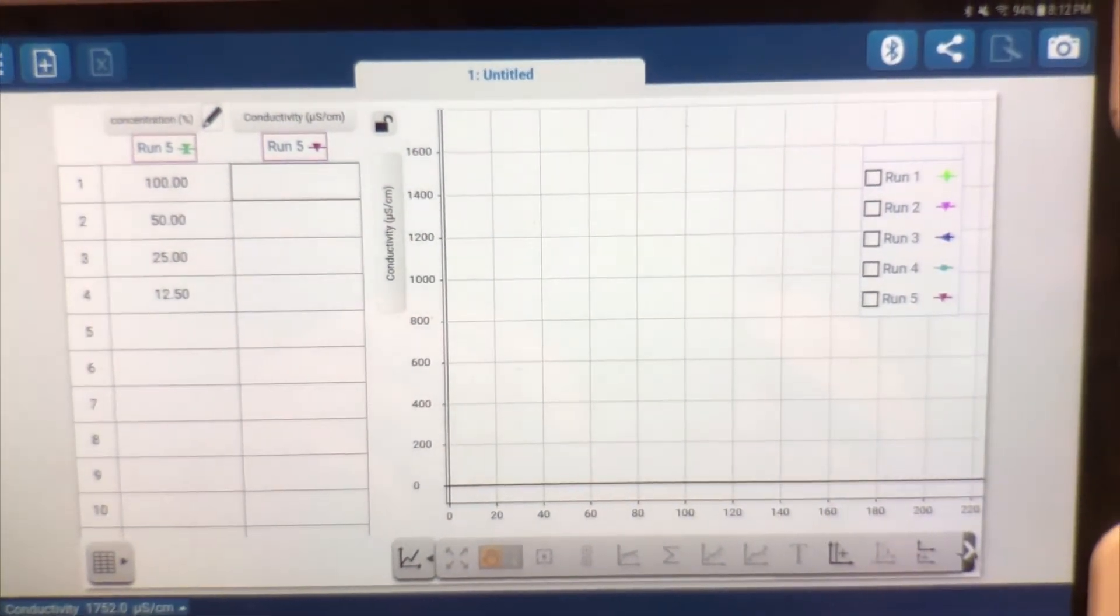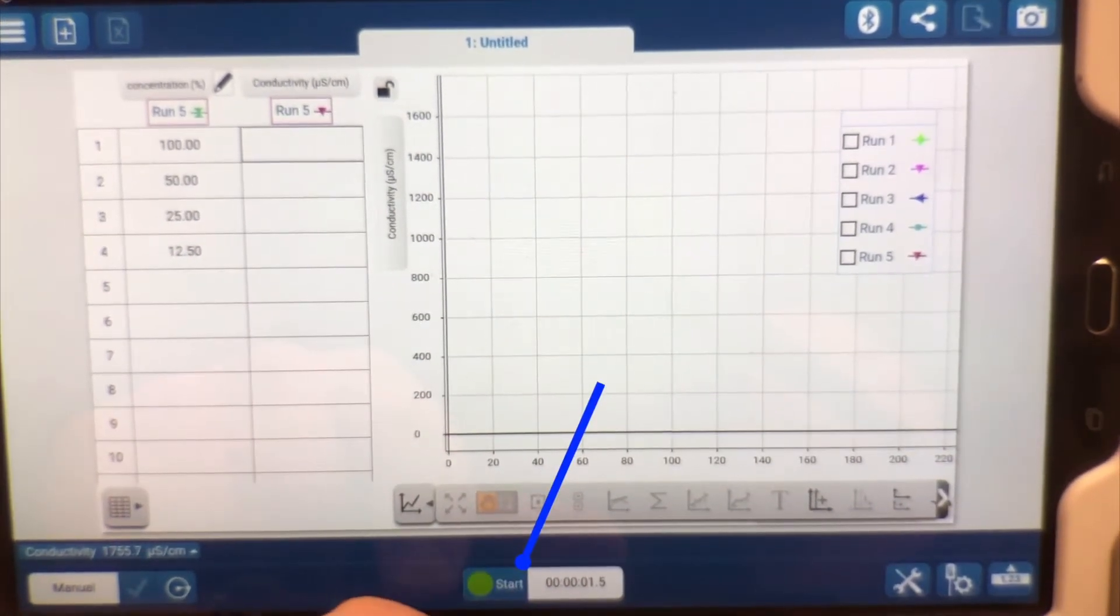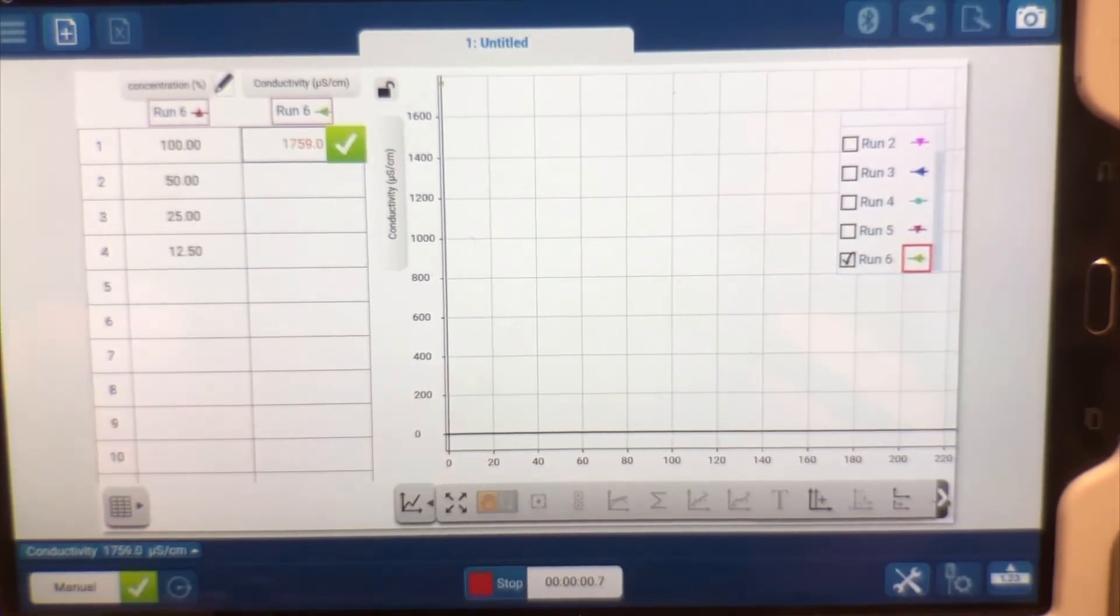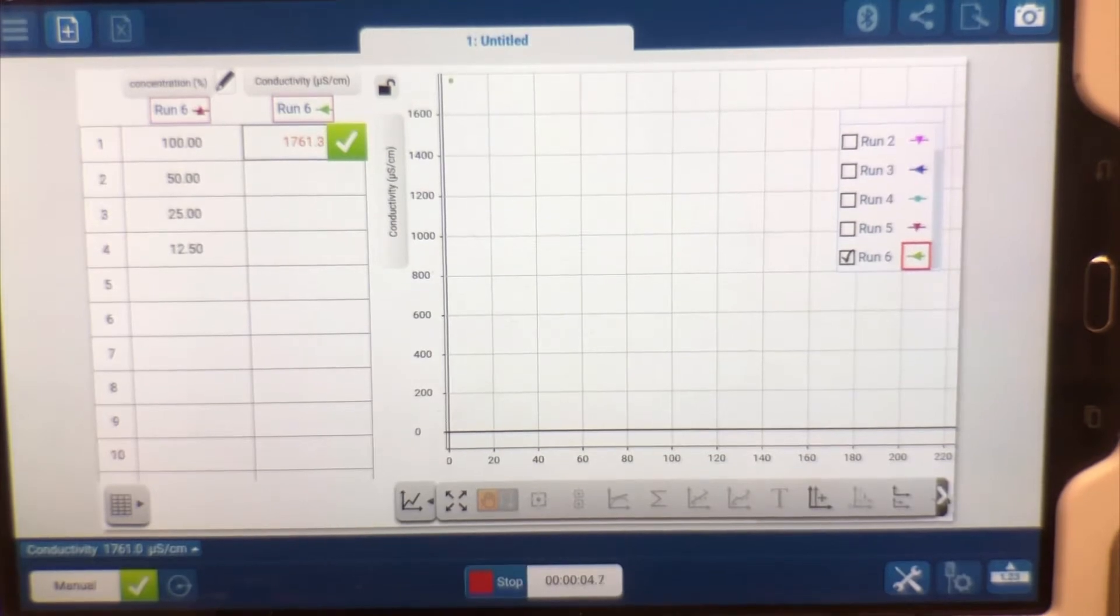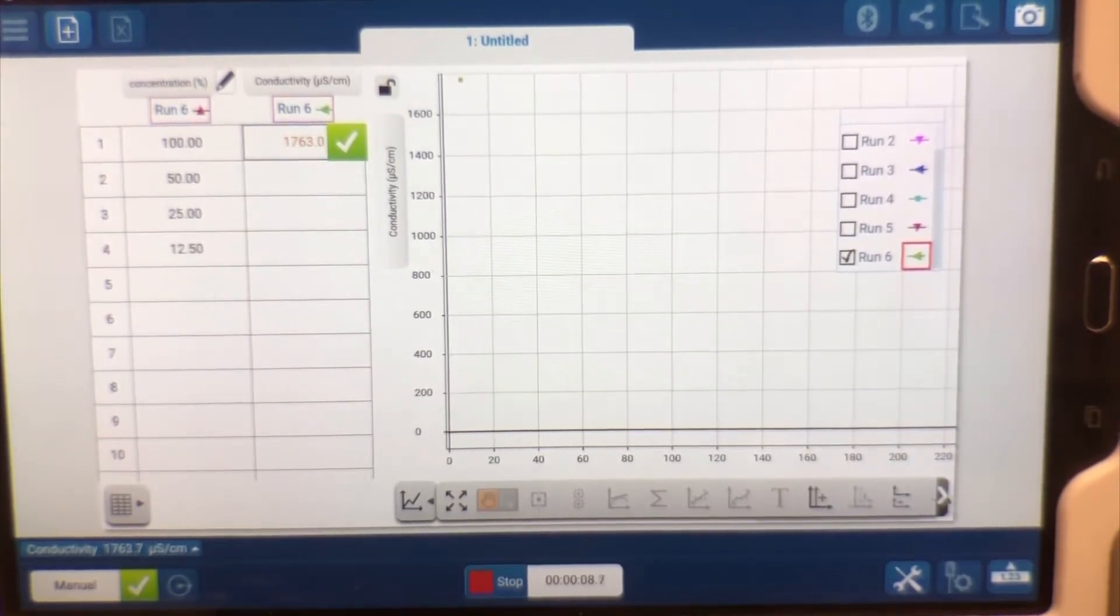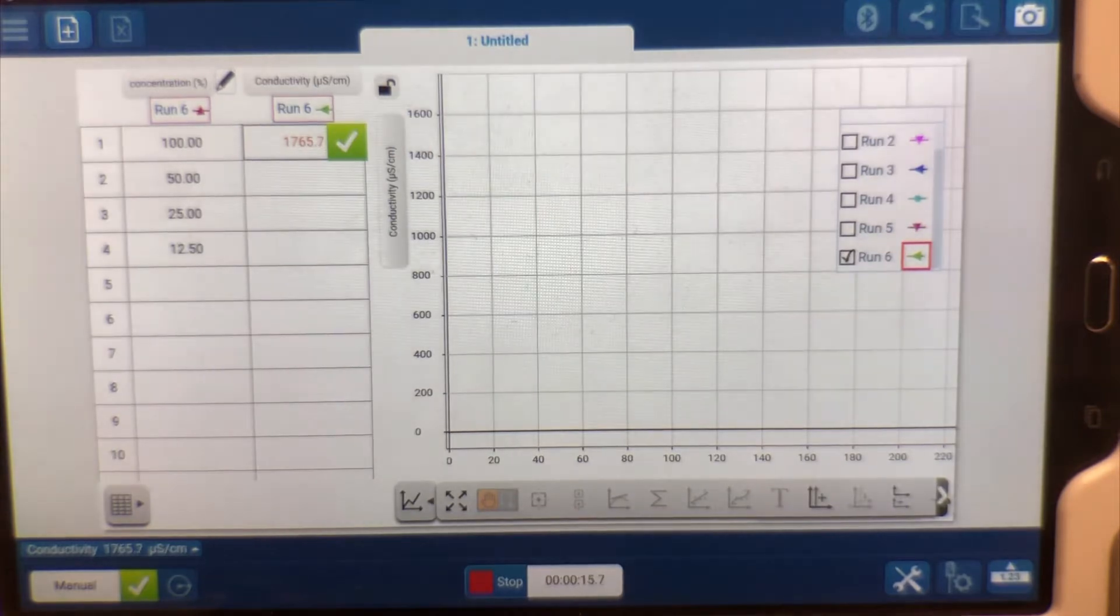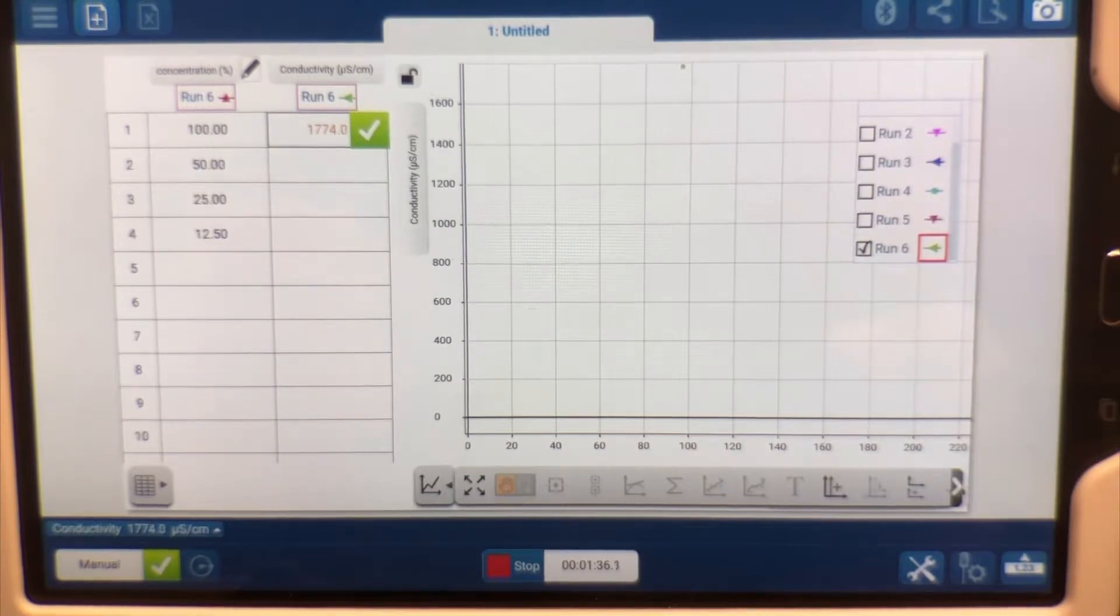When we have that all lined up then we're going to hit start. It's right here on the bottom. See that right there? I'm going to hit start. And now what it's doing is it's recording its first run. Actually this particular app has been used several times so that's why we're on run 6. So it's about 1764 µS/cm, we're going to let that run just a little bit longer to see if indeed it starts to settle down. Now that our first set of data with 100% concentration is settled down we're now going to move it to the next one, the 50%.